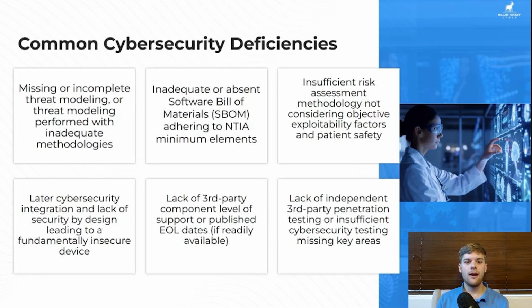Now, a very, very common problem is late cybersecurity integration, and lack of security by design just leads to a fundamentally insecure product. If we start going through our risk analysis and we identify tens of thousands of findings, which seems like a lot, but it does happen, that indicates problems systemically through the product. What went wrong to allow this many vulnerabilities to work their way into the system? And obviously, remediating 10,000 vulnerabilities is a massive effort compared to remediating 50 or 10. We want to make sure that cybersecurity principles are employed early. We aren't leaving this to the end. We aren't trying to retrofit security into the product.